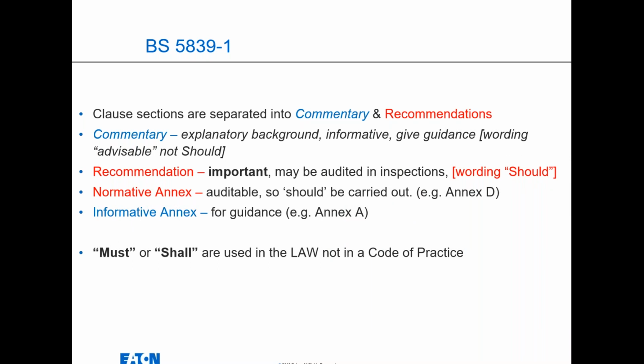So 5839 itself, there are lots of commentaries, lots of recommendations. Must or shall are used in the law, not in the code of practice. So as I said earlier, this is recommendations, and therefore it can be treated with some understanding that not everything can fit, so you might have to put a variation in to a design. But as long as you make a note of that variation, then that's quite acceptable. As long as it's quite pretty reasonable.